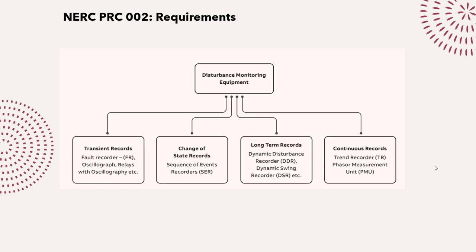Long-term records use dynamic disturbance recorders or dynamic swing recorders, with durations ranging from minutes to hours depending on the recording facility requirements. There are also continuous records such as trend recorders, phasor measurement units, or SCADA systems, which continuously record at a specified rate, have larger storage capacity, and provide wider visibility of the power system.